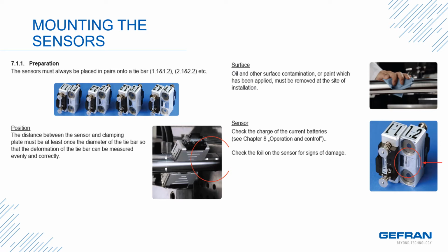Lastly, the picture in the center shows two sensors mounted 180 degrees from each other. The sensors must be mounted at least 1 tie bar diameter away from the clamping plate. This enables a correct and accurate measurement. The sensors are now ready for the machine to open and close and take readings.